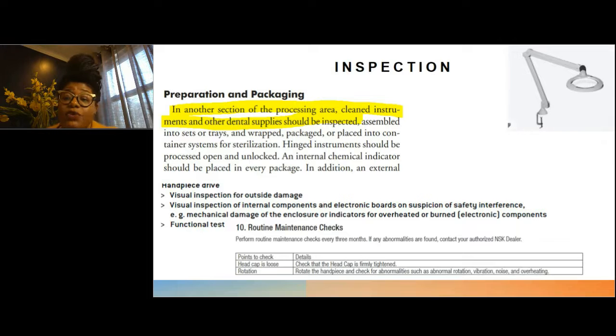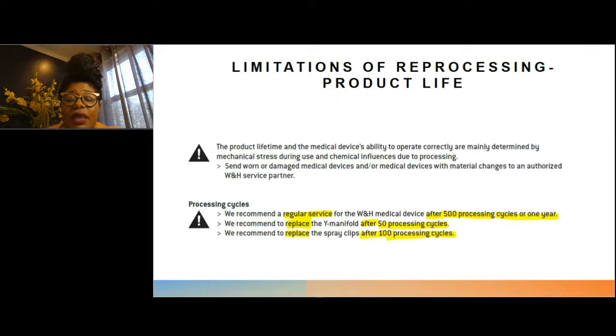Inspection is key. If you do not have the inspection part in reprocessing, you do need to incorporate that. You will find that your IFUs will have an inspection portion. Then limitations for reprocessing: your IFU will provide you with that information. If components of your handpiece or device have a life, the manufacturer is going to tell you how many times you can reprocess it. After that many times, you've got to get rid of it and get a new one.